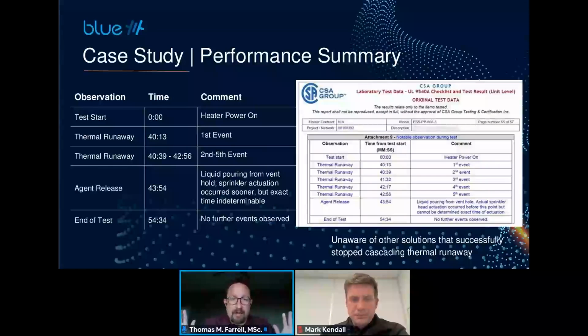And they considered end of test about 10 minutes later because there were no more thermal events. Things were substantially cooling. And then they let that rack sit exactly as it was for a minimum of 24 hours. And not only did this module not reignite because the thermal runaway hazard was successfully managed, nothing else went into thermal runaway either, because again, the heat was being handled by blue.